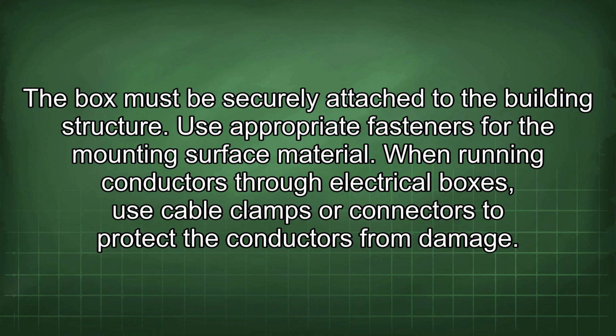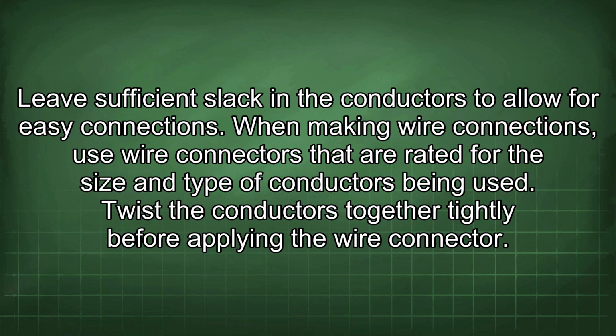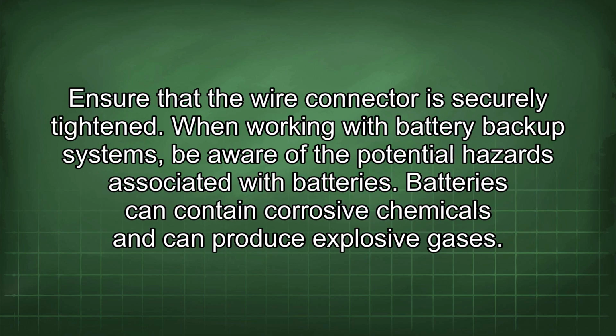When running conductors through electrical boxes, use cable clamps or connectors to protect the conductors from damage. Leave sufficient slack in the conductors to allow for easy connections. When making wire connections, use wire connectors that are rated for the size and type of conductors being used. Twist the conductors together tightly before applying the wire connector. Ensure that the wire connector is securely tightened.